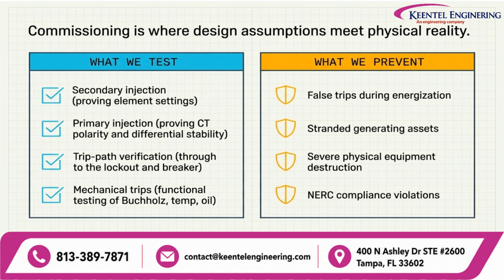The mechanical protection functions must also be tested. This can include Buchholz protection, temperature protection, and oil-related protective functions. The purpose of commissioning is not simply to prove that the relay works. It is to prove that the complete protection chain works.